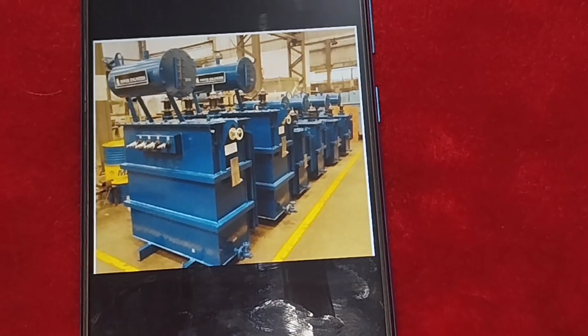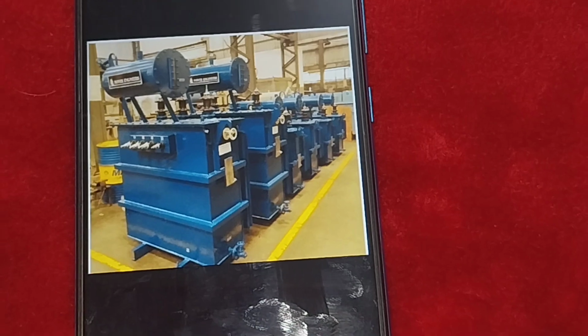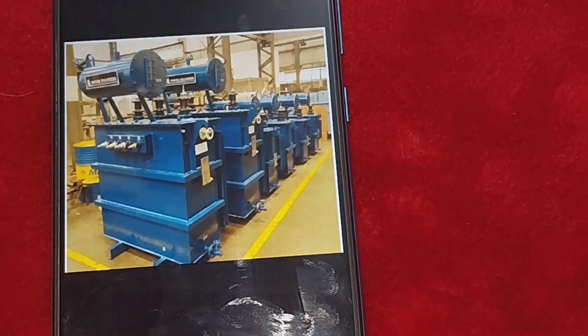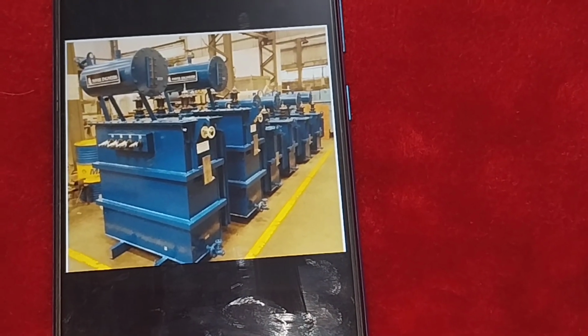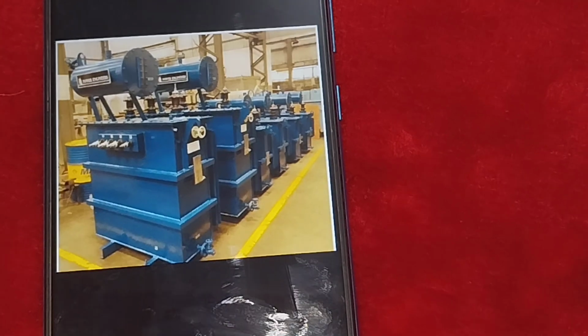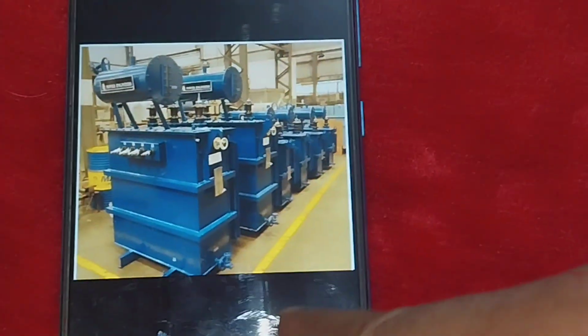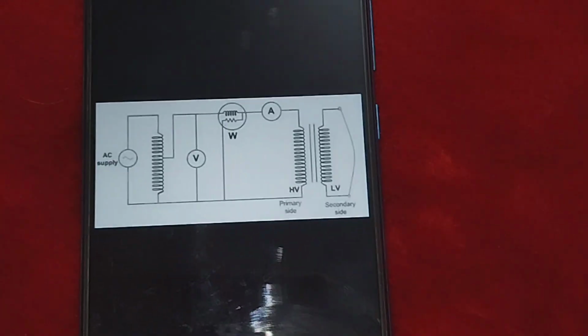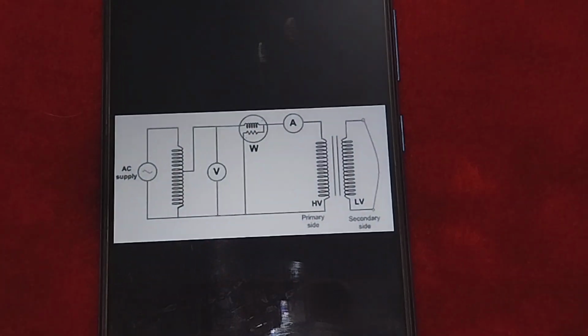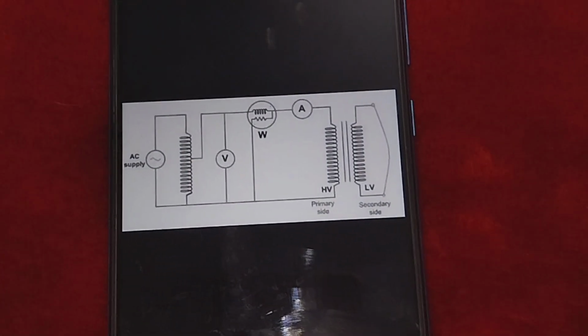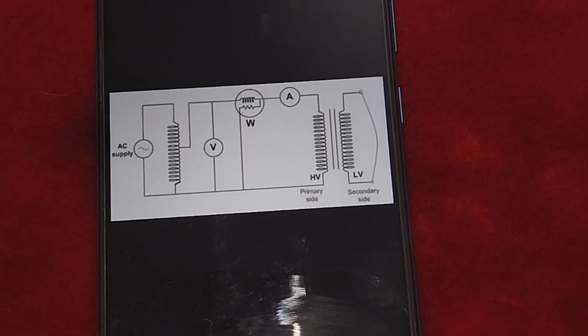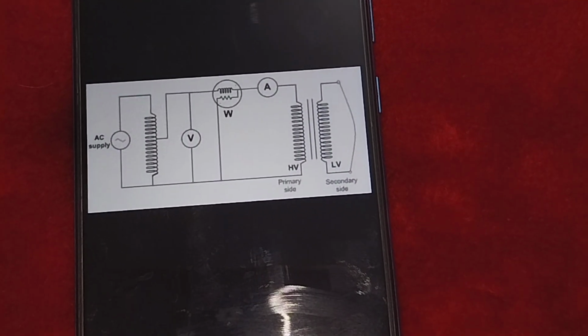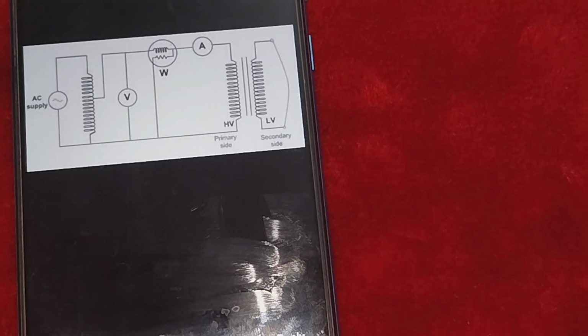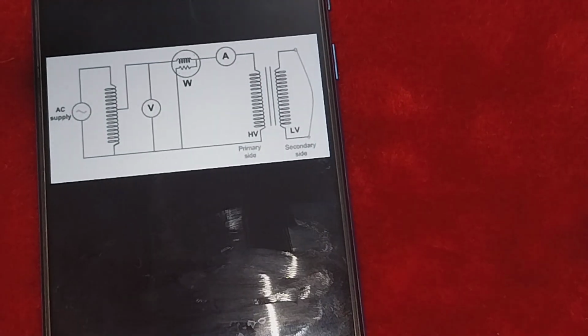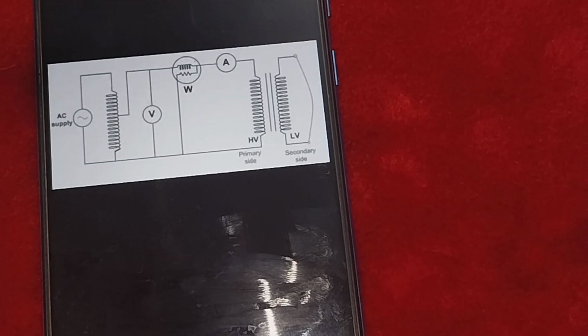Then there is voltage ratio test, partial discharge test, turns ratio test, test for vector group, open circuit test, short circuit test, and heat run test. Heat run test is actually a type test done to ensure the output capacity of the transformer. Then there's the test for DC resistance of the winding.